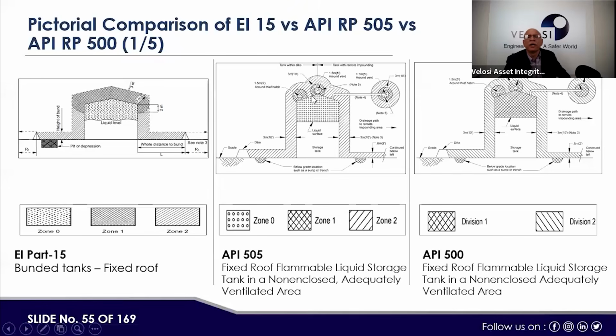If the breathing valve, they're marking the zone up to 1.5 meter, and then up to 3 meter, they are marking zone 0, zone 1, and zone 2. Similarly, there they are saying division 1 and division 2. Like here, this and this part, zone 0 and zone 1 in these two standards are called division 1 in API 500. This was the old concept.